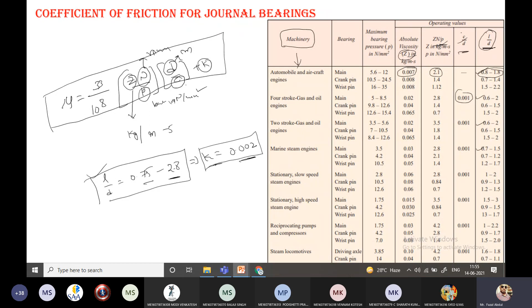From the table, the L by D ratio for the centrifugal pump, as the question mentions, lies between 1 to 2. So 1 to 2 means we can select 1, 1.1, 1.2, up to 2. I am selecting 1.6. Your wish, Babu, there is no condition to select only 1.6; you can select any value. Now L becomes 1.6 into D. We don't know the D value, so I am assuming D as 100 mm. Now what is the L value? 160 mm. This first point is over.